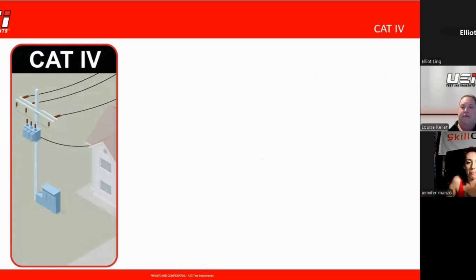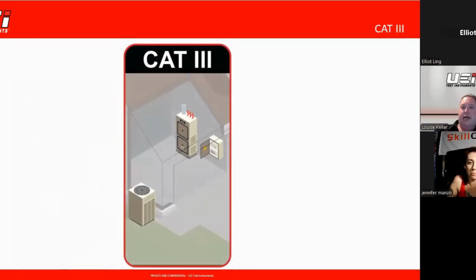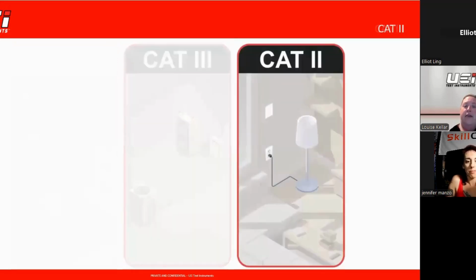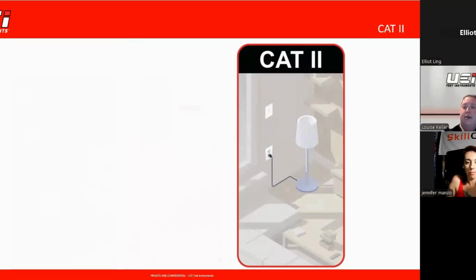A category 4 meter is designed to work on anything coming from the power line into the box at the house. Category 3, which is primarily what we're working on in the residential world, covers from the fuse box to either the outlet or a hardwired appliance. Category 2 covers from the outlet to the actual appliance.